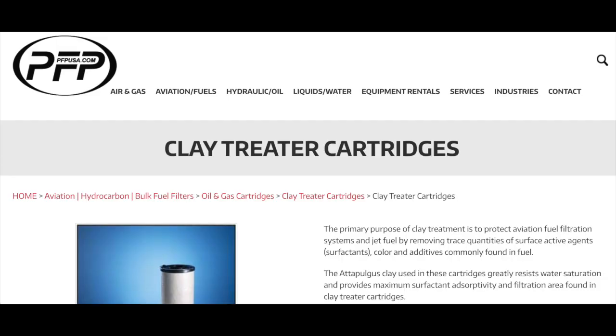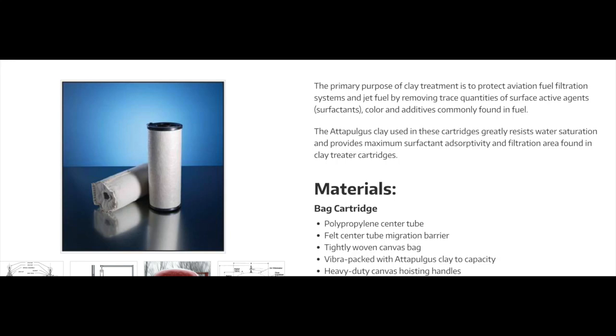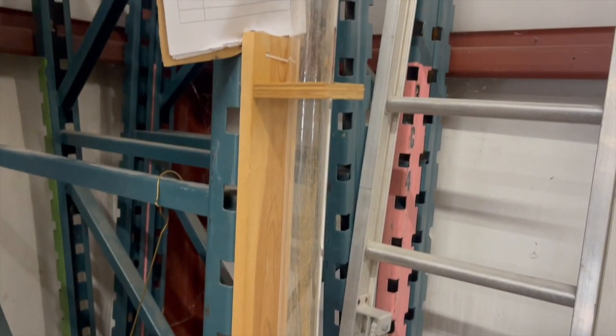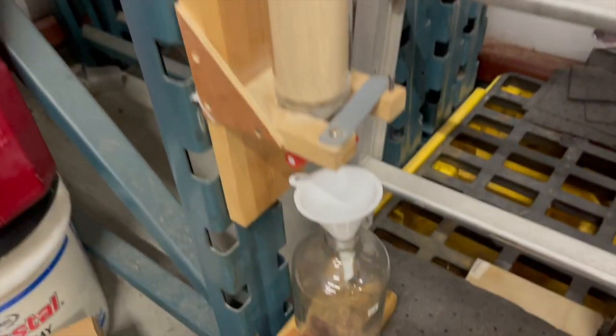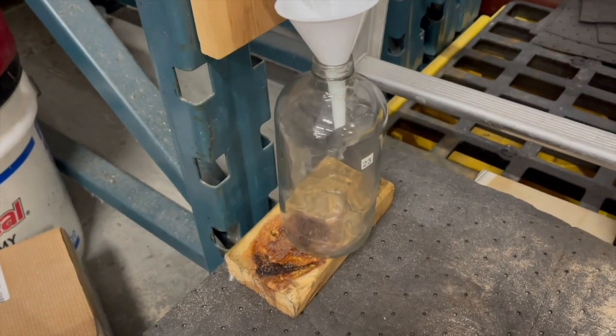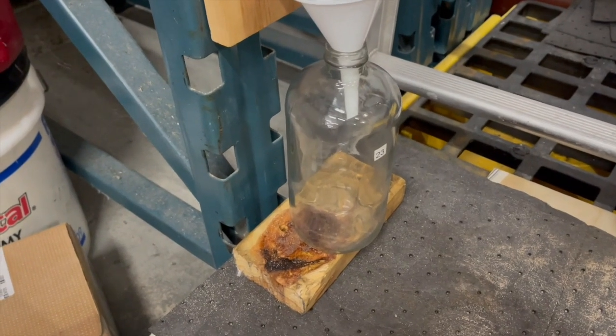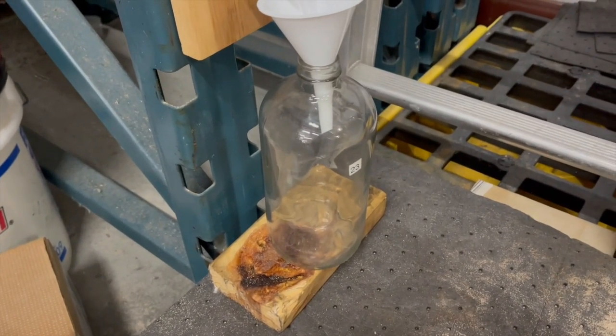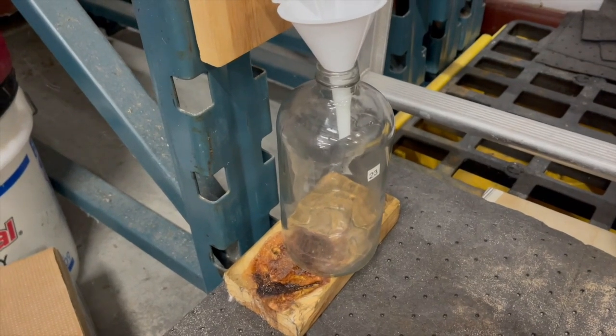The clay we use is Attapulgus clay. It comes from clay treater cartridges, and we use it to filter the kerosene. This makes the kerosene into very low conductivity jet fuel, as it removes all of the surfactants and other things in the fuel that raises the conductivity, making the fuel very clean. What we do is we pour the fuel into the top here, it goes down, filters through the clay into the glass bottle, and then once that glass bottle's full, you have zero fuel, which is fuel that is somewhere around 0 to 10 picosiemens per meter.